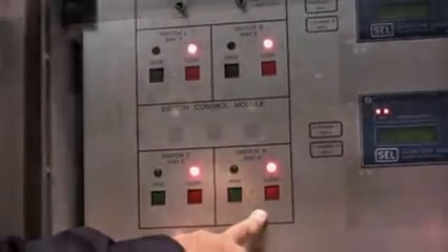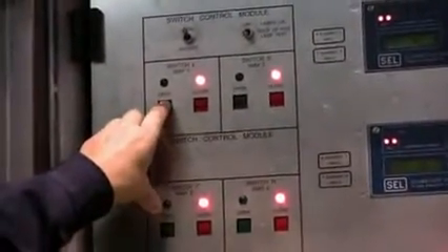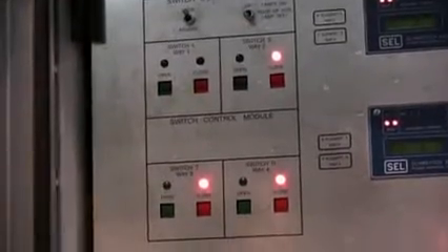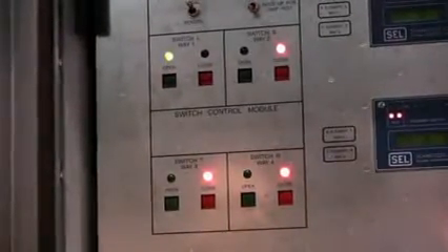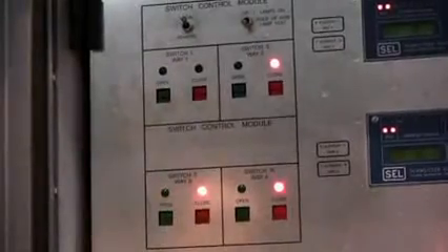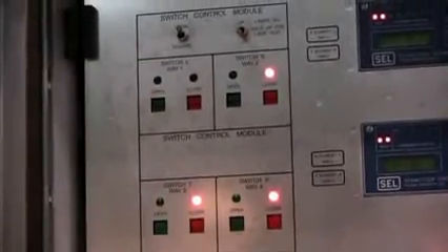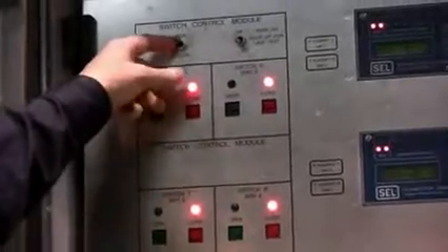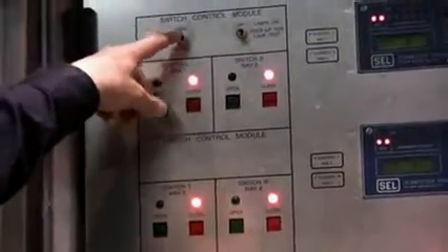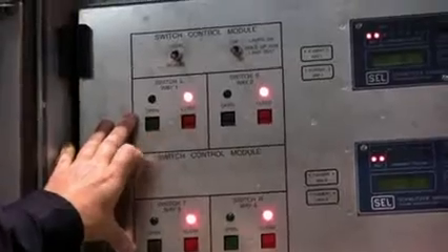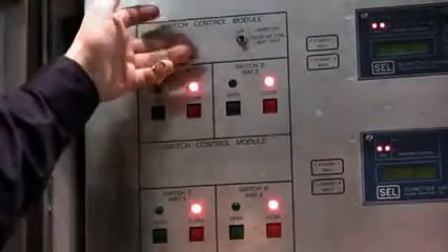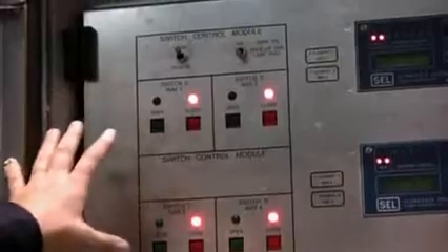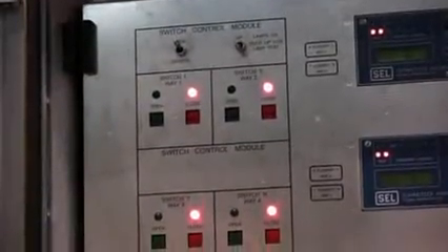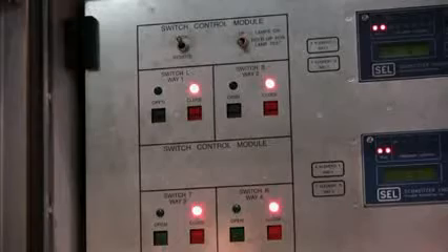You'll notice we have lights here for our motor operators. All 4 ways are locally controlled. And now I can open way 1. And then I can close way 1. We have a local remote switch, so when it is in remote, you have no local operation. It's all operated by SCADA. When you put it in local, you have local operation, and it also goes back to the SCADA master and says that the device has now been put in local operation.